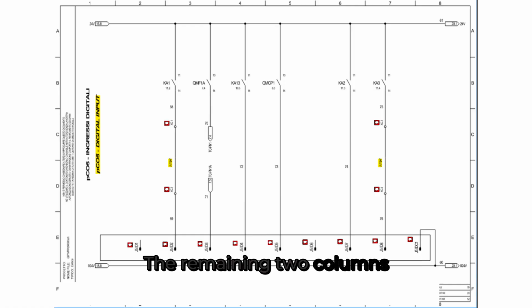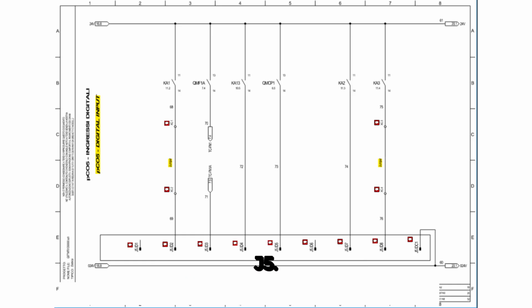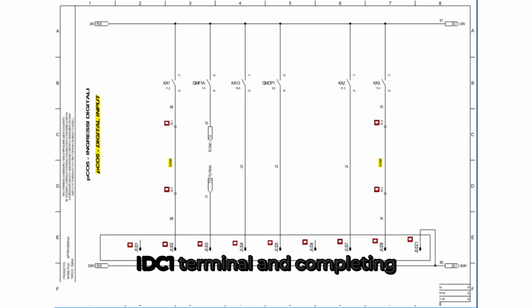The remaining two columns show Ka2 and Ka3, which are the safety interlock relays for the Circuit 1 low-pressure switch and Circuit 2 high-pressure switch. The 24-volt common return is shown at the far right, connected at the J5 IDC1 terminal, completing the input loop and returning to the transformer ground reference.